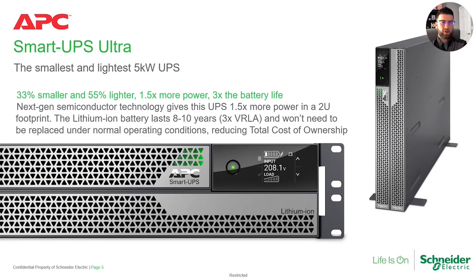So without further ado, let's look behind the curtain and understand what the Smart UPS Ultra 5K is. In short, it's a unit that is more than a third smaller and more than half the weight of the comparable lead-acid 5 kVA product you know today. Unlike the SRT 5K, you do not have to replace the batteries — the lithium ion battery lasts as long as the UPS itself, making it as close to a set-it-and-forget-it approach as you can imagine. And when looking at purchase price, yes, this product carries a premium upfront, but when you extrapolate the expenses throughout the lifetime of a UPS...